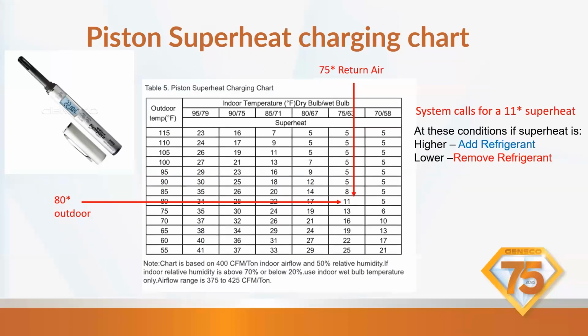Here's a superheat charging chart. This is in the install manual. You have dry bulb and wet bulb up here. So dry bulb would be your temperature probes in there. If you need to take a wet bulb, you're going to need a psychrometer. I recommend this one. Gensco does carry a FieldPiece. I carry that one around too. It makes it easy.